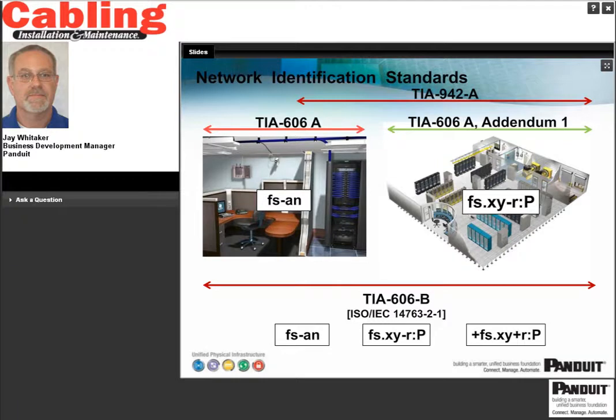The designation for panel positions in a cabinet or rack can either be an alphabetic designation or, preferred, a 2-digit number that represents a rack unit number, or RU number, where the top left mounting screw lands in the cabinet or rack. By using the RU method, this provides the data center manager with greater flexibility since it allows for panels and equipment to be added or moved later and not disrupt the designation of panel identifiers. This identifier would define that the top left mounting screw of the panel is located at the rack position B in the cabinet or rack located at the intersection of row AR and column 15 in the data center.